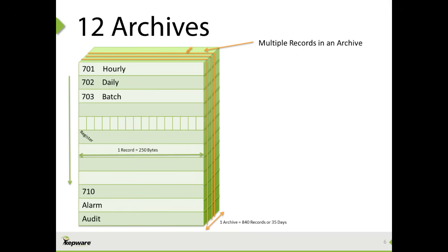These records can be split up into finer detail on what we call registers. You might have registers in the Flow computer that contain certain information like average pressure or temperature, and each register takes up a section of that record, and each register takes up 4 bytes. This is how our archive is going to be split up and segmented, and in a moment we're going to see how these record numbers and register numbers correspond to information that you need to enter into KEPServerEX so that we can properly get this information.